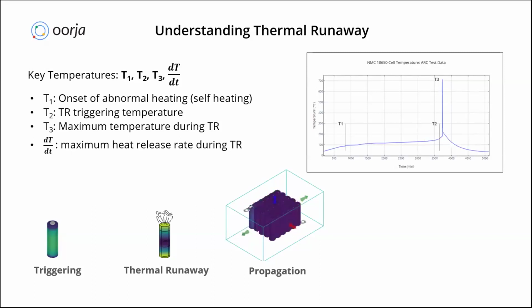Whenever a cell starts going into thermal runaway, first there will be different types of exothermic reactions happening inside the cell. Because of these reactions, there will be uncontrollable heating inside the cell, which will lead to thermal runaway. T1 is the onset of abnormal heating, T2 is the thermal runaway triggering temperature, and T3 is the maximum temperature a cell can reach during thermal runaway. Based on these three temperatures, these are the signatures that decide how that cell's thermal runaway performance is going to be.